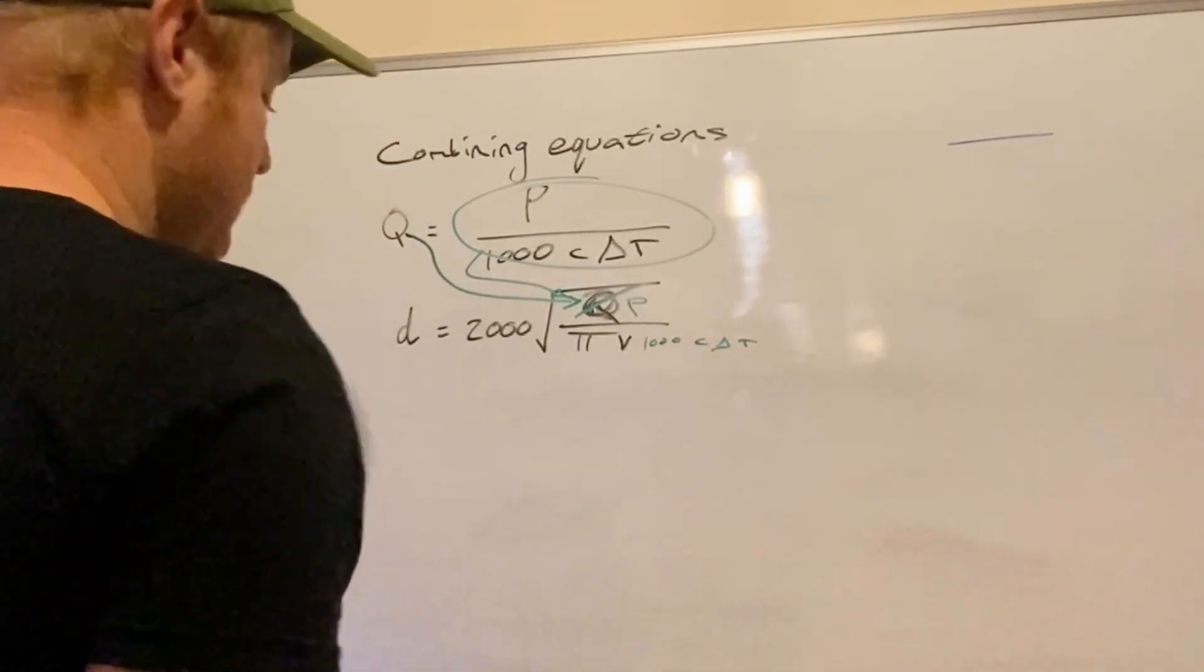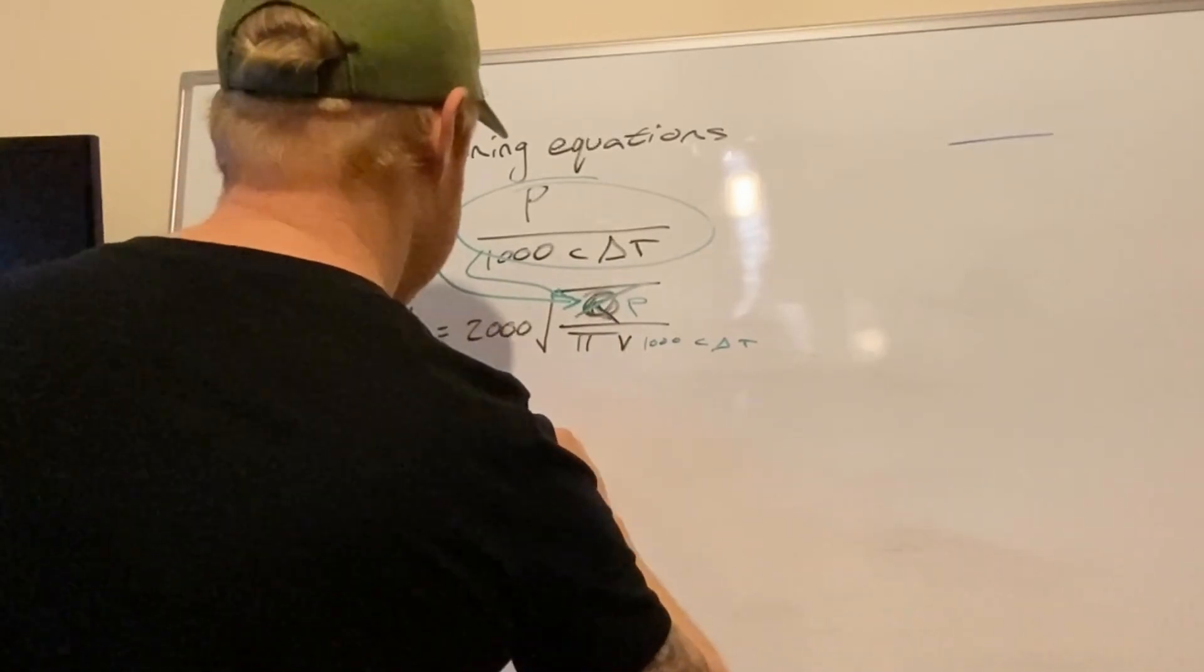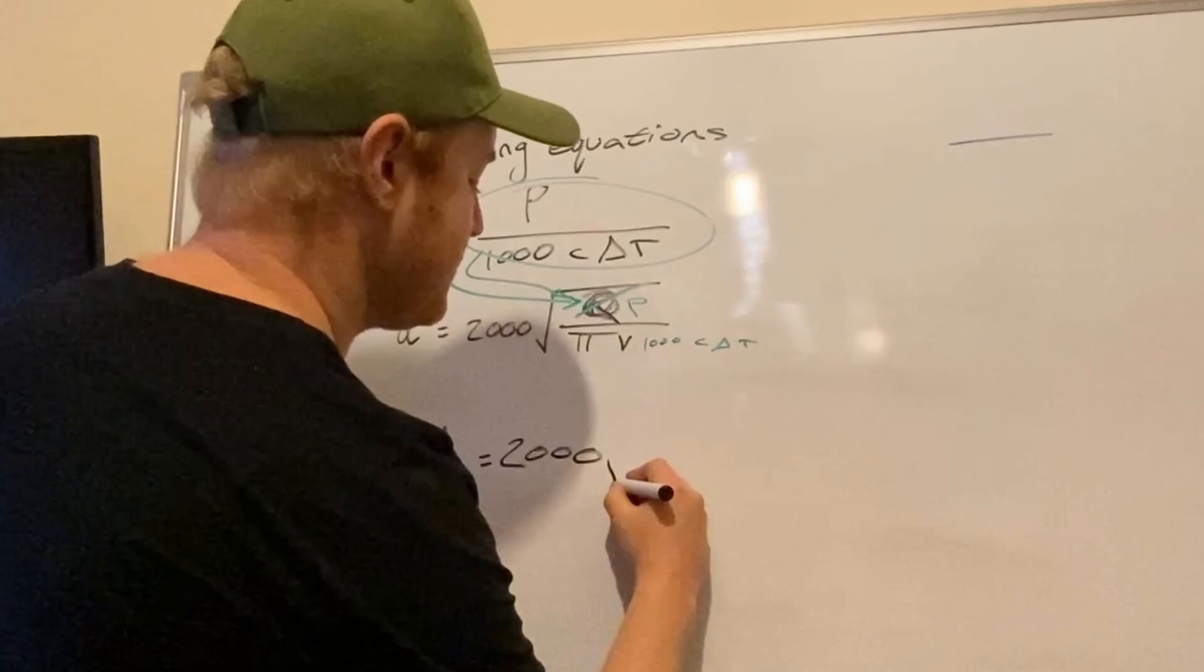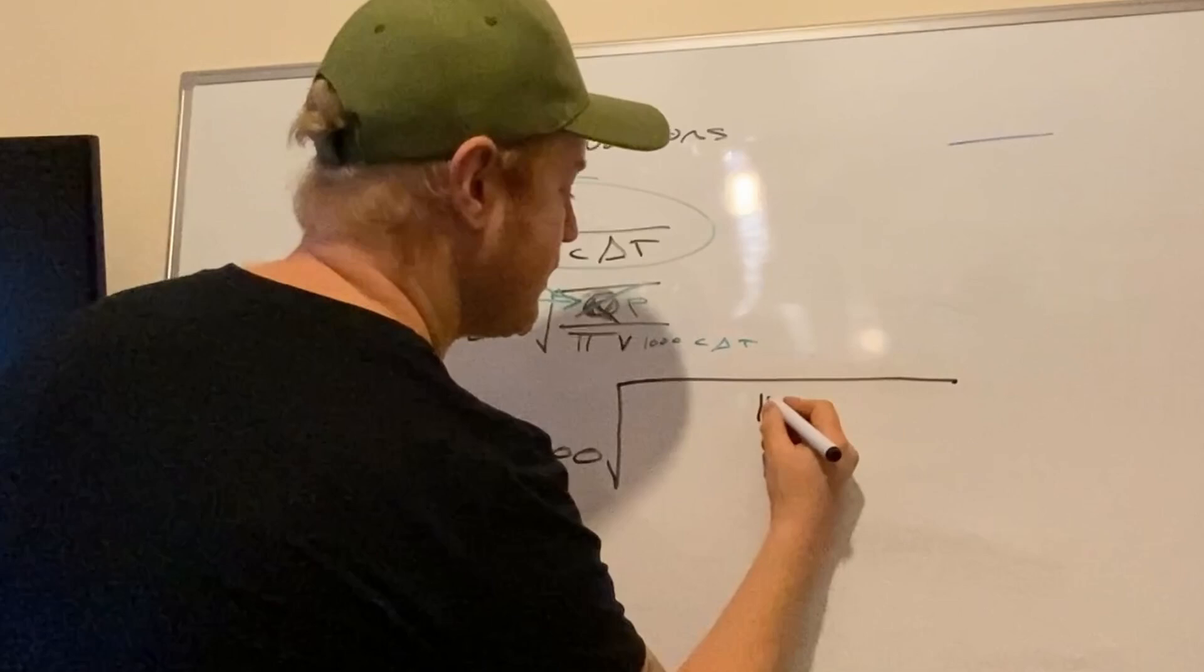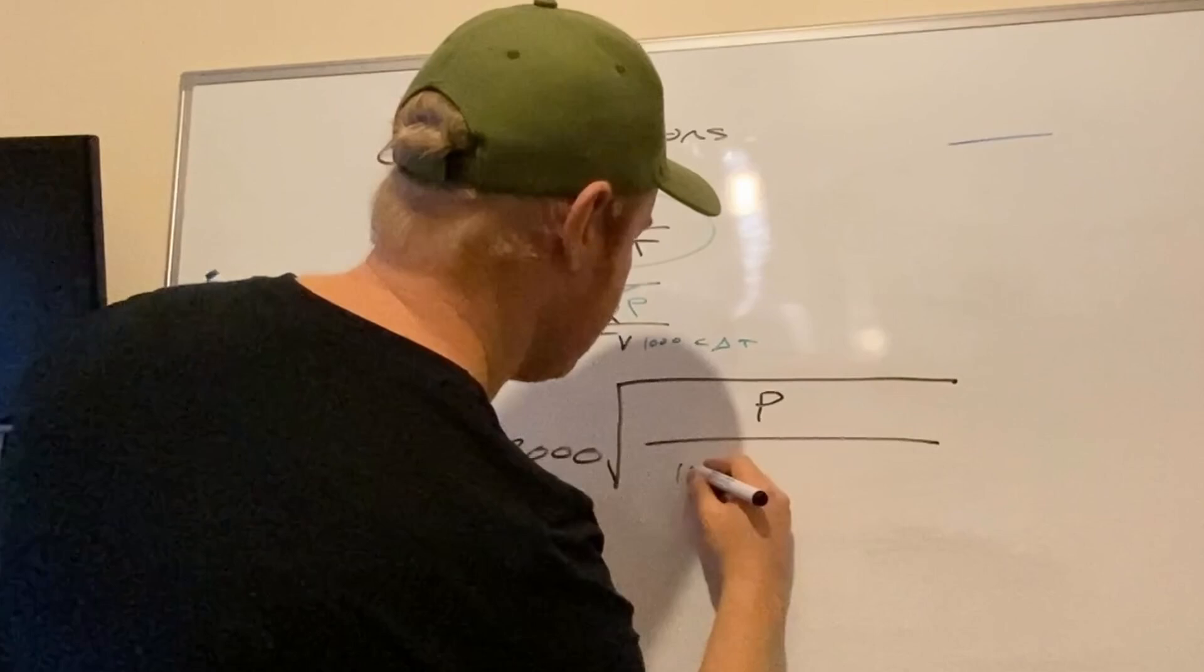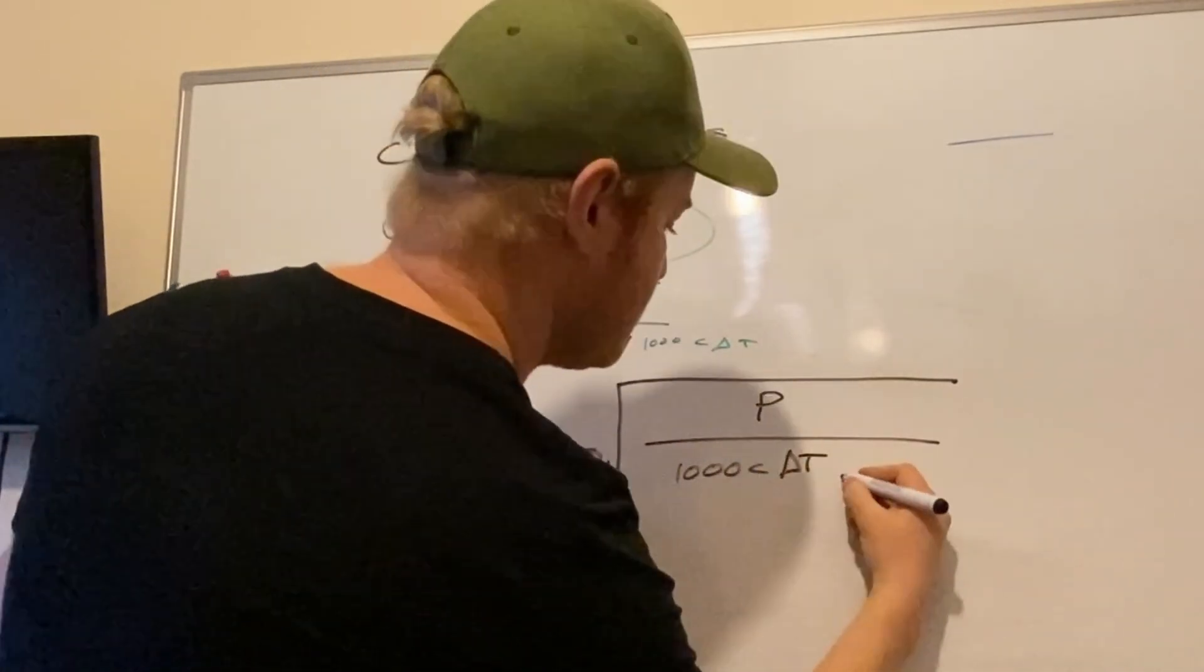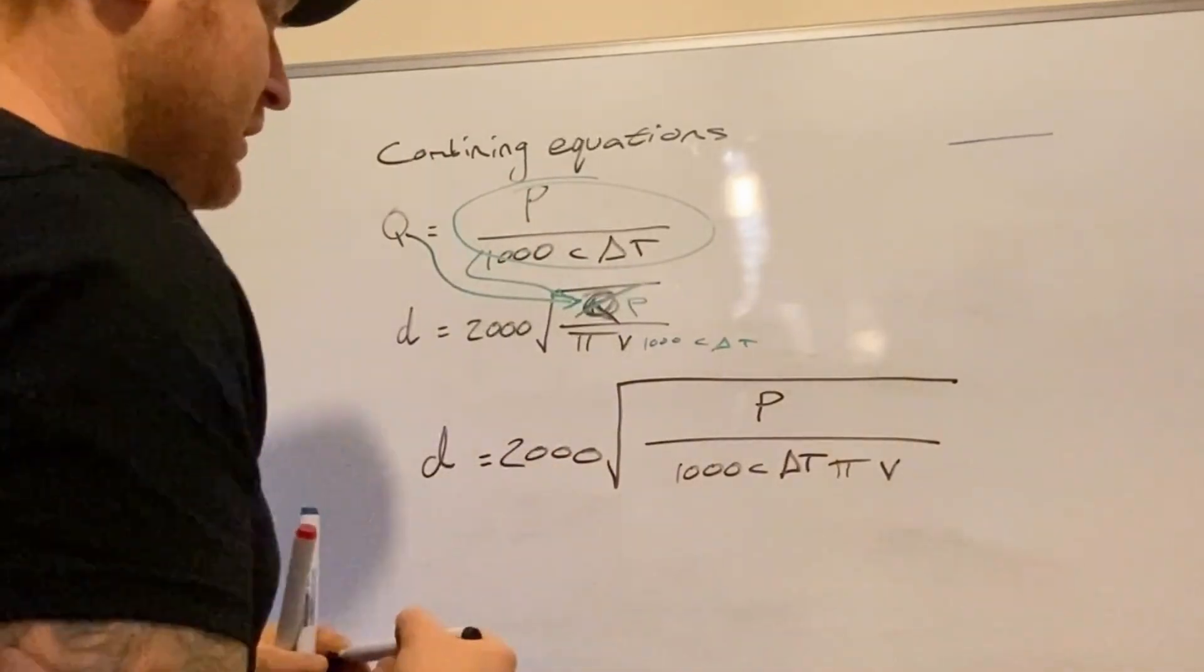So if we write out longhand, the longhand equation is diameter equals two thousand times the square root of power divided by one thousand times specific heat capacity times delta T times π times velocity. And that's it.